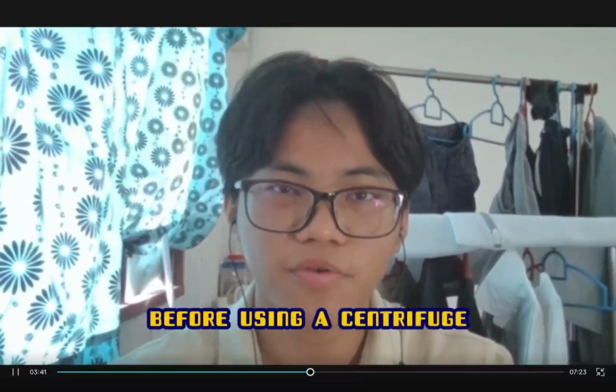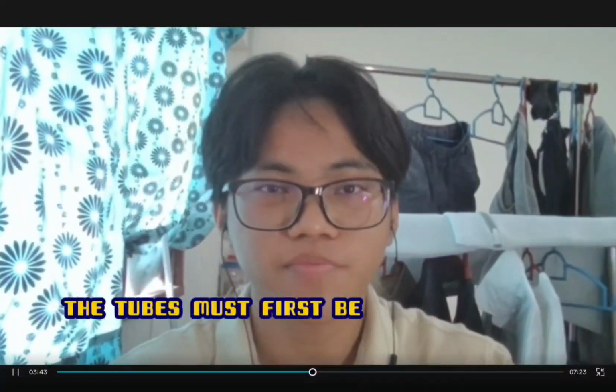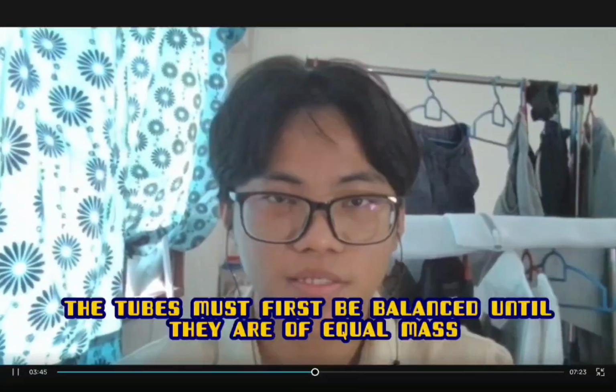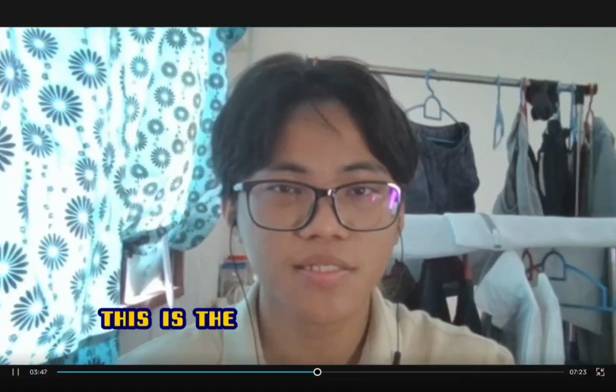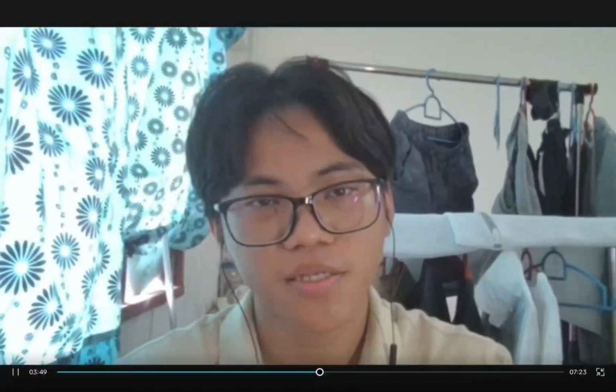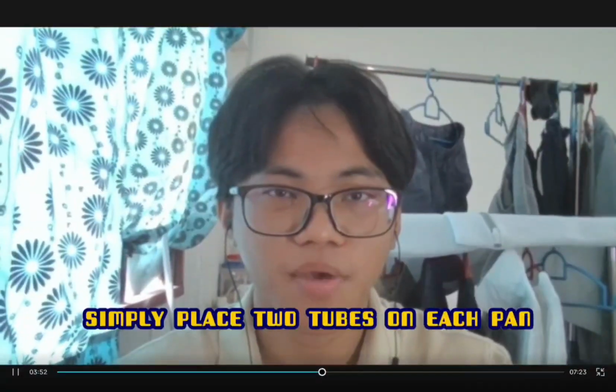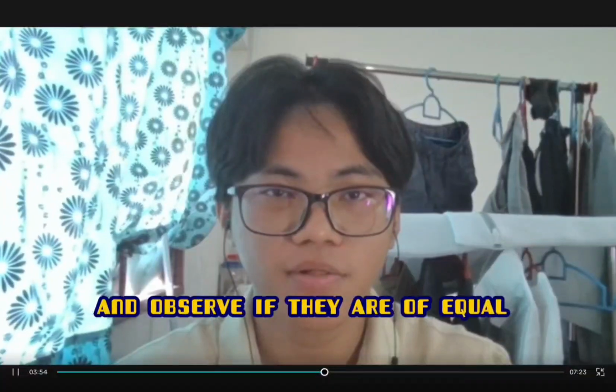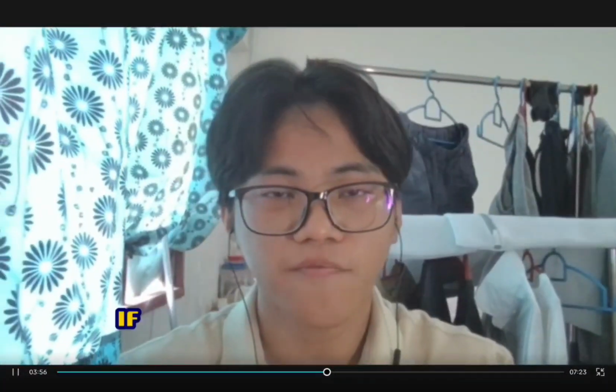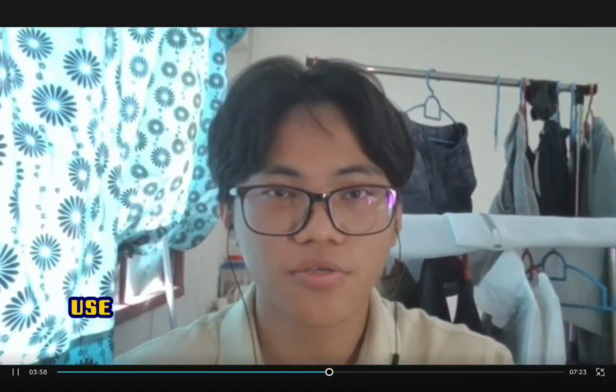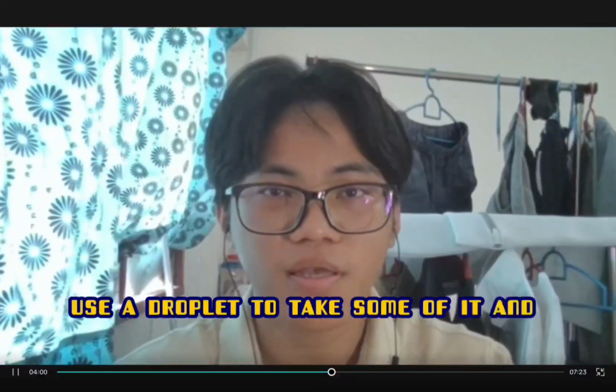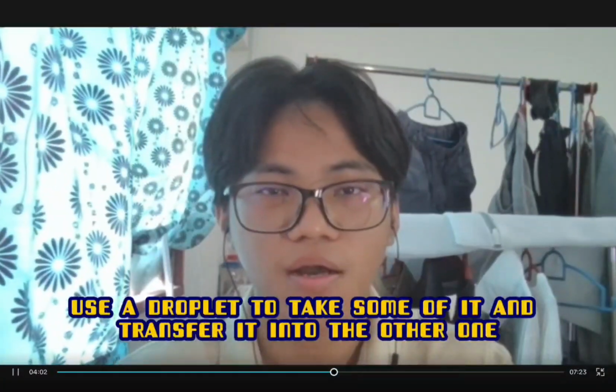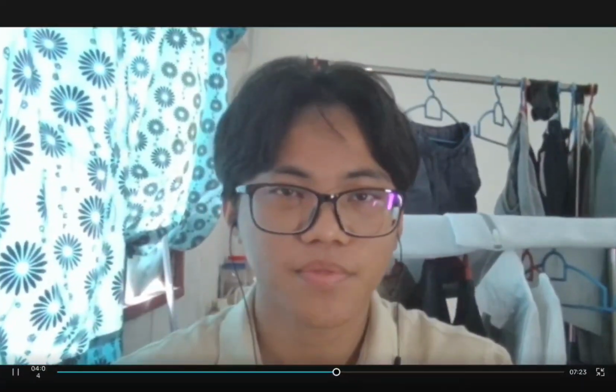Before using a centrifuge, the tubes must first be balanced until they are of equal mass. This is the purpose of a beam scale. Simply place two tubes on each pan and observe if they are of equal height with each other. If one is lower than the other, use a droplet to take some of it and transfer it into the other one until they share the same height.